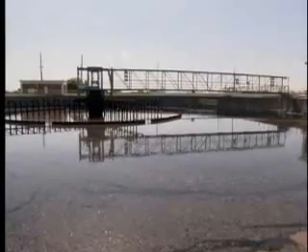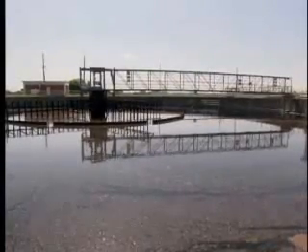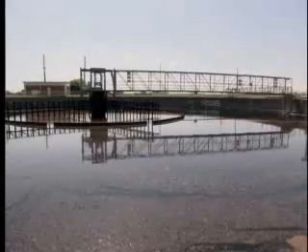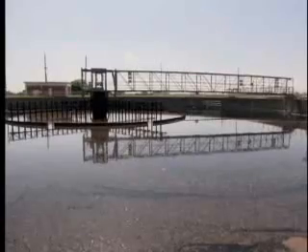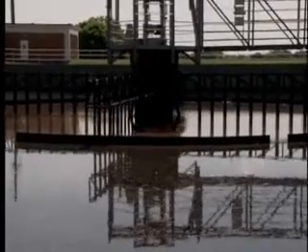And in this tank we add oxygen, and here's where we accumulate bacteria that use the waste and the wastewater as their food and produce carbon dioxide and water as byproducts. This is the final clarifier or secondary clarifier. The activated sludge at the end of the aeration process is directed to this tank, and the mixed liquor, which is the contents of the aeration tank, called mixed liquor suspended solids, settles out in this clarifier.